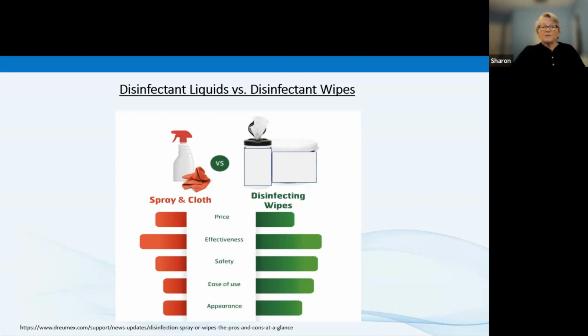Care of surface and equipment. There's a correct and an incorrect way to disinfect surfaces or equipment. And if users aren't trained for this, repeatedly spraying a liquid on the surface can lead to expensive repairs or permanent damage. Disinfectants should always be sprayed onto a cloth and not directly on a surface. Now, you may leave a paper residue. When a spray bottle is combined with paper towels, and some places do this, it can leave a paper residue. And this can lead to additional work to remove that paper. This can also have negative consequences on the effect of the disinfectant if that paper residue isn't removed.